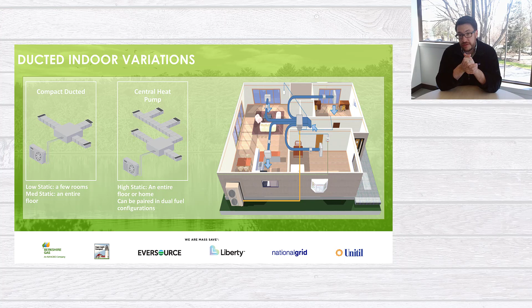In addition, with the centralized heat pumps, sometimes they can also have components that can help out with resiliency as well as redundancy. They can have an electric heating element built in that if the heat pump is ever completely covered in snow or there ever is a polar vortex, the electric heating element can kick on and take over. In addition, ducted heat pumps can also be sitting right on top of an oil-fired furnace or a gas-fired furnace. So there is a lot of flexibility with thinking about ducted heat pumps as a dual fuel type of configuration. If someone is just feeling a little bit nervous about the technology, it still can be an option for that homeowner.